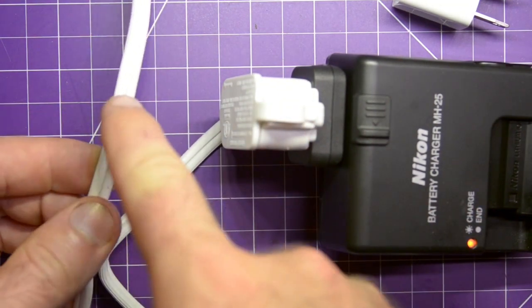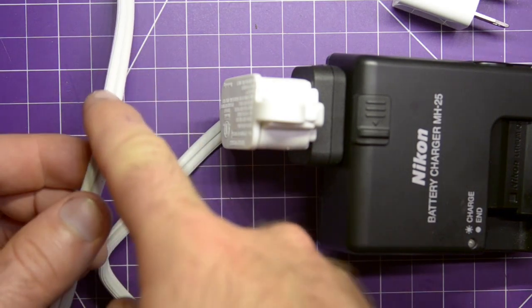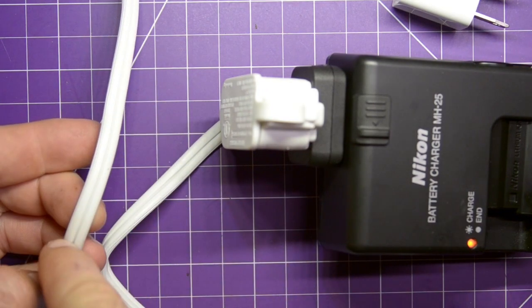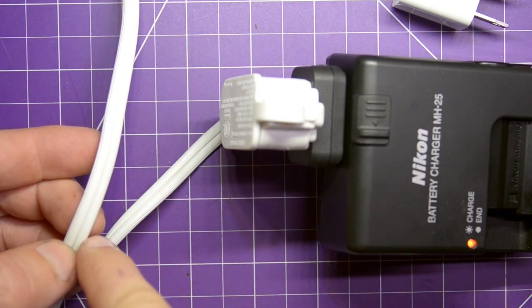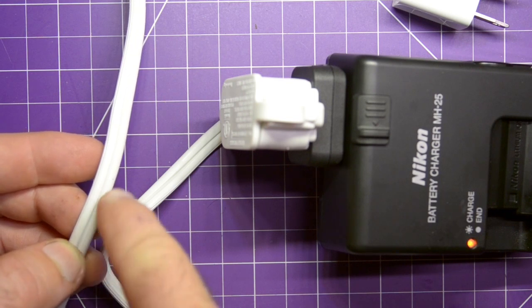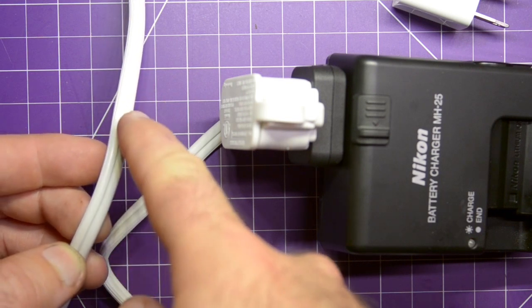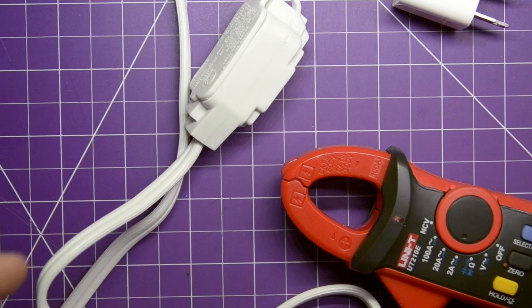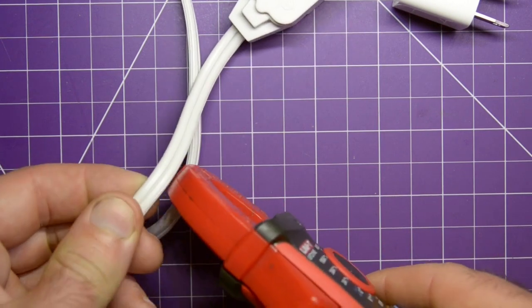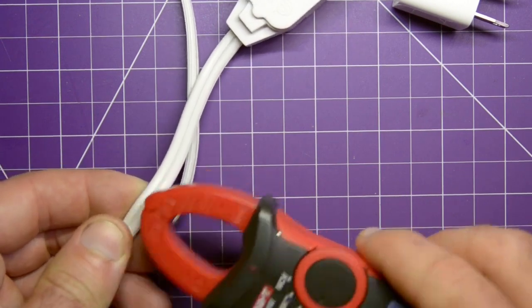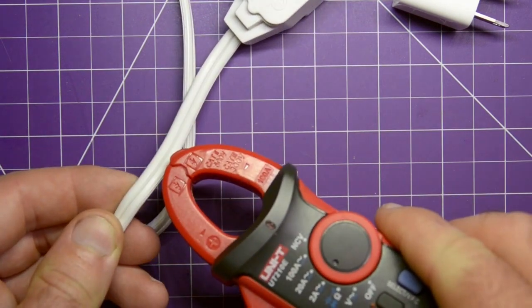And so, although there might be some amperage flowing this way in this wire, there's also the same amount of amperage flowing this way in the second wire. This means that somehow we're going to have to get this clamp over only one of these two wires.